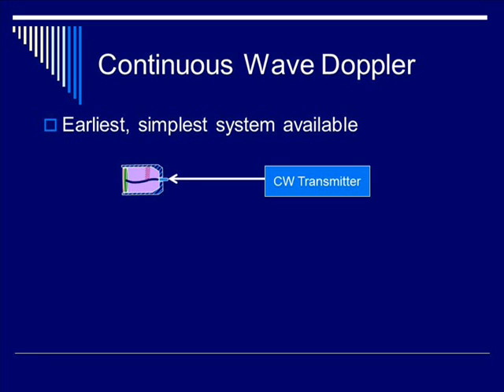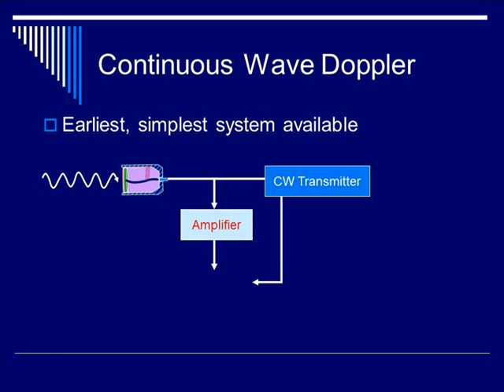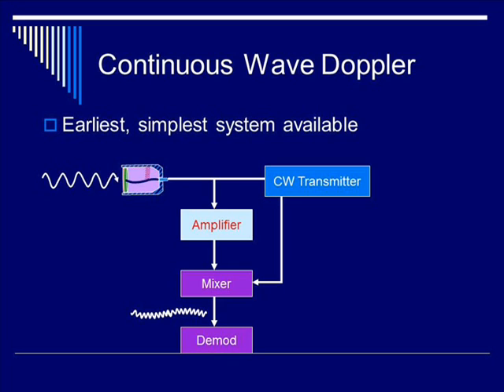The continuous wave Doppler is the earliest and simplest system available. You have a continuous wave transmitter or oscillator feeding a signal to the transducer. The returning signal comes back, is amplified, and mixed with the original oscillator's transmitter signal through a mixer, which multiplies the signals into a product. The resulting signal is then fed through a demodulator and a wall filter, yielding the low-frequency Doppler signal.